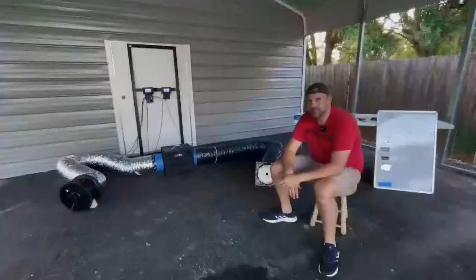Today's test had to go outside because I made a homemade smoke box. Word to the wise, don't use caulk. I caulked the inside of that box three times over, no good. Had to get in there with a bucket of mastic, paint it up twice over. That's the only way I could get that box to seal under pressure, was using mastic. So if you're gonna make a homemade smoke box, use mastic. All right, so what's going on out here?